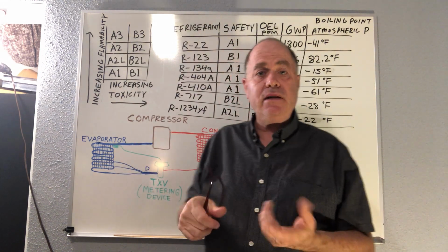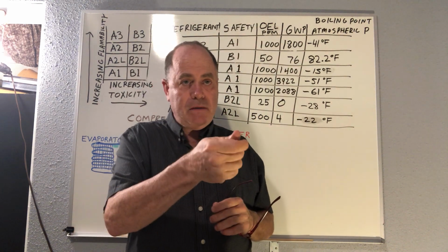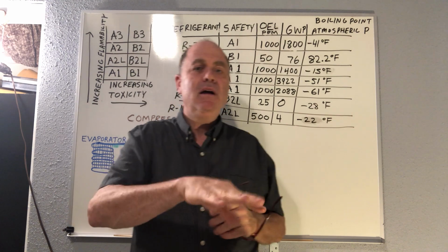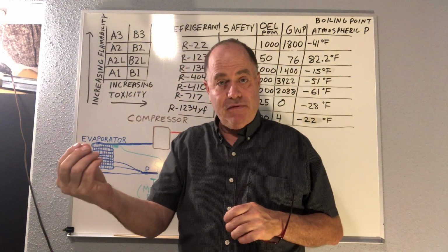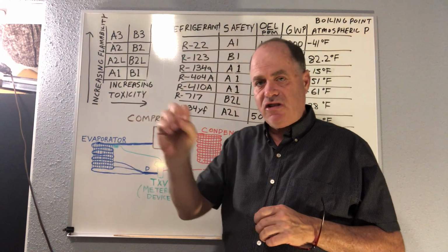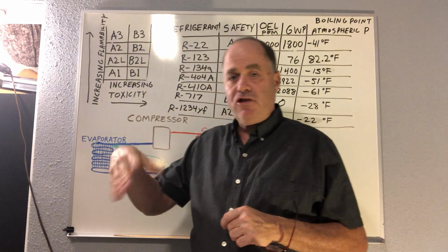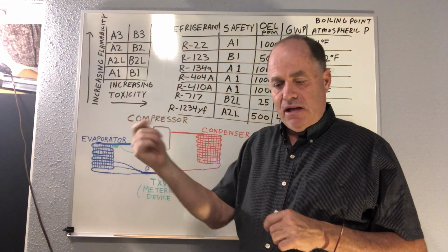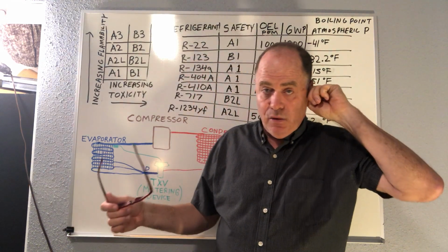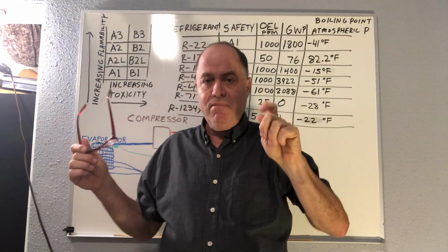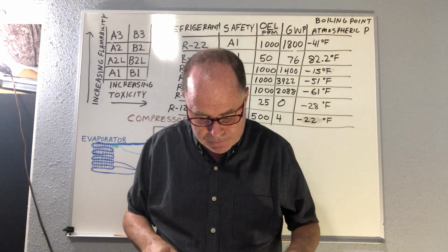And in order for them to pick up and go off, because it goes beep, beep, beep when it hits a leak, you need to have a sample of that refrigerant in there with the nitrogen. It's just a tiny little bit, and it will mix with the nitrogen, and then as it leaks out, it would help you find the leak. So they'll allow that, and then we do tend to just vent out the nitrogen with a minuscule amount of refrigerant in it when we're done. Okay.